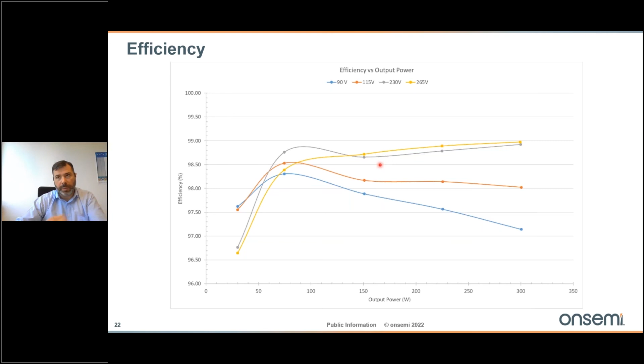Here, I would like to highlight the value at 50% load. As you remember from the first slides, the 80 Plus Titanium standard requires up to 96% efficiency at 230 volt input at 50% load. Here we are quite well above, more than 2.5% higher than that specification. And this is very important for efficiency and power consumption.